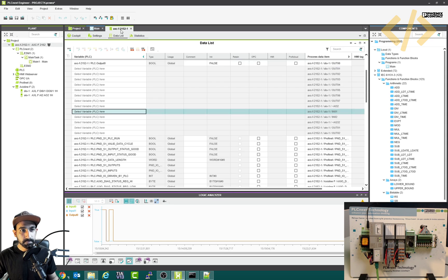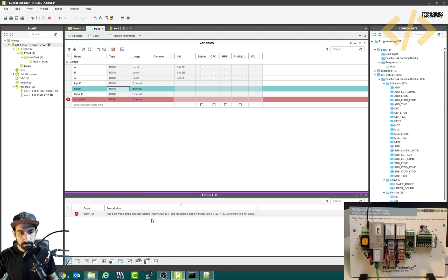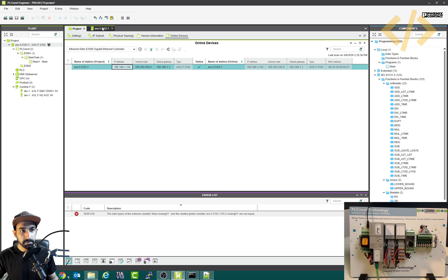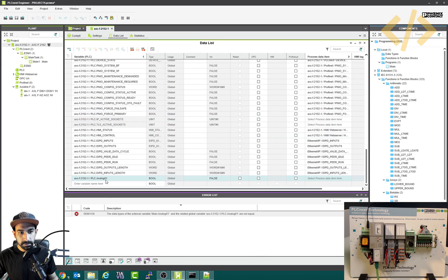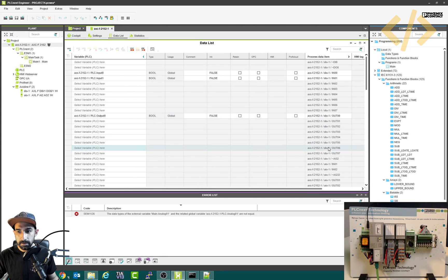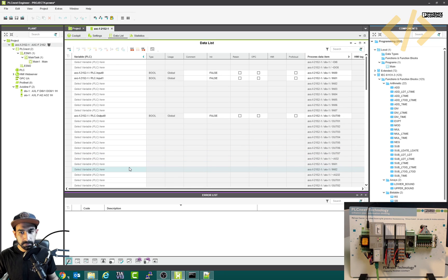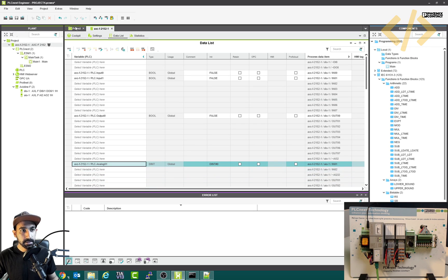There's an error — the data types are not equal. Going back to check, I defined the data type before and it caused a problem. I'll delete the previous 'analog zero' which was defined incorrectly. Now coming back here to analog input zero one, I'll select 'analog zero one' which I defined in the PLC. Now this double integer variable is linked to my external analog input.